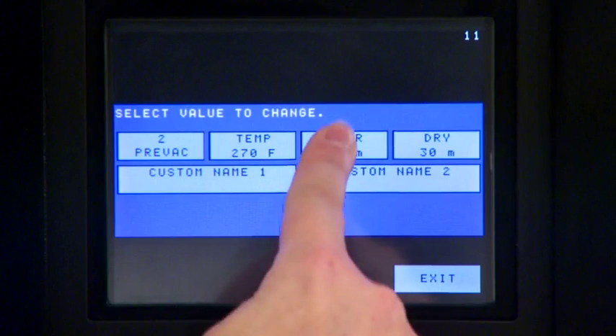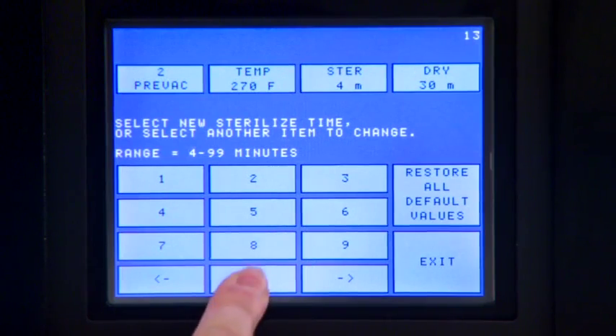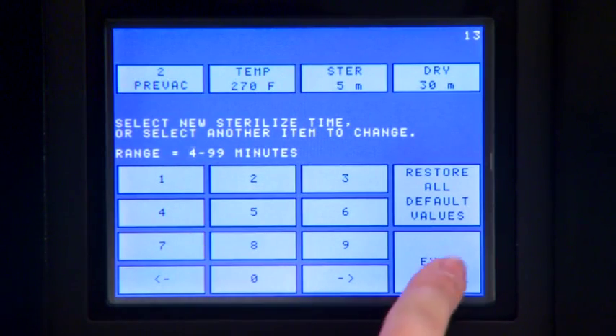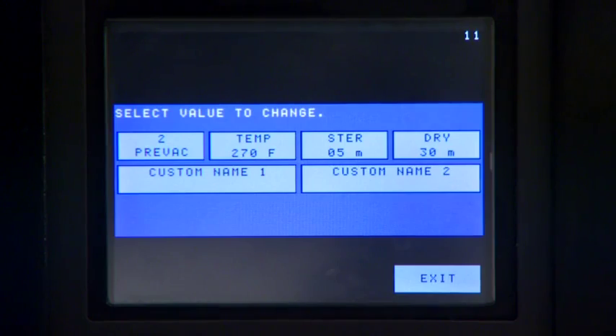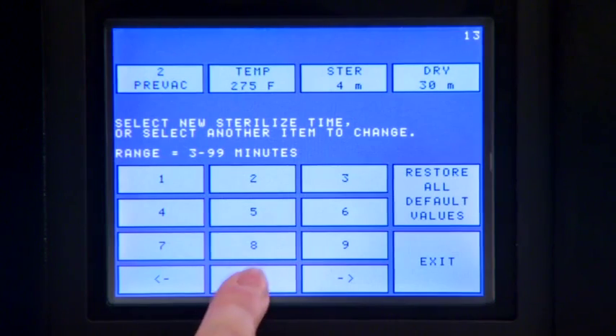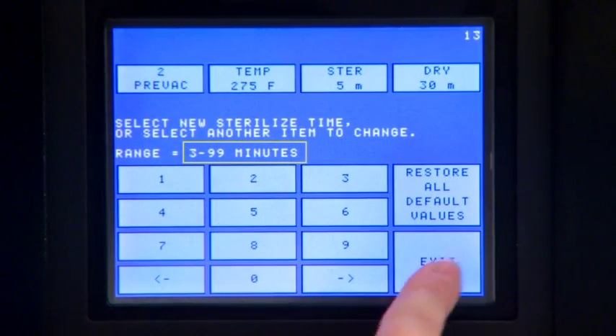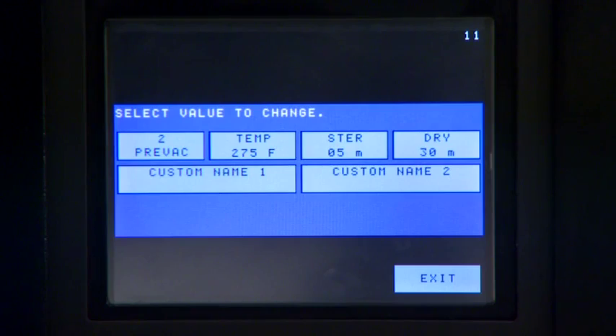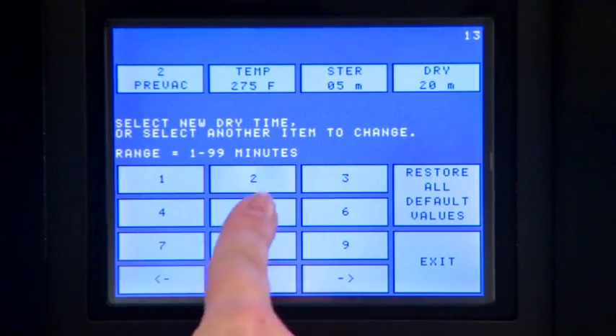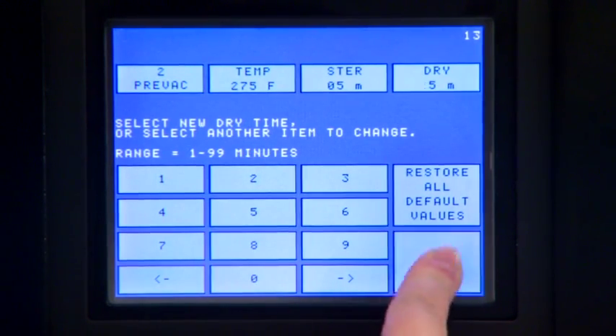To adjust the sterilized time for a 270 degree Fahrenheit Prevac cycle, enter the new value ranging from 4 minutes to 99 minutes. A 275 degree Fahrenheit Prevac cycle is adjustable from 3 minutes to 99 minutes. To change the dry time, enter the new value using the same range of 1 minute to 99 minutes.